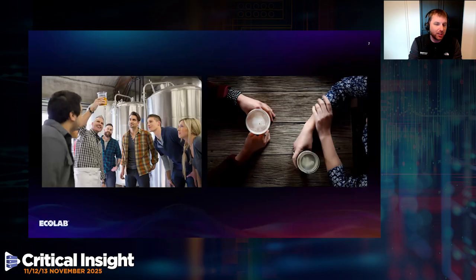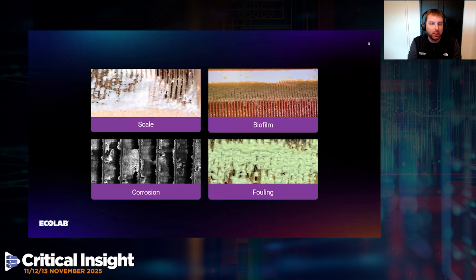The same is really important in direct-to-chip cooling. The issues we don't like to see on the cold plates directly attached to the chips include scale, biofilm, corrosion, or general fouling. Given the really small fins, often copper or aluminum, and the large surface area with a low volume of water, small issues can quickly overwhelm the system if not tightly controlled.